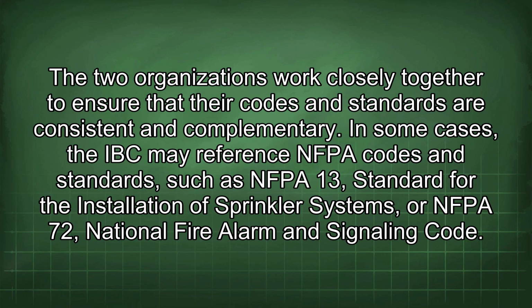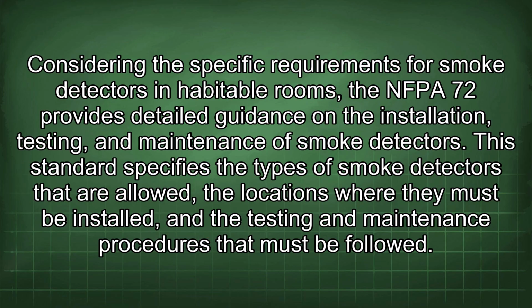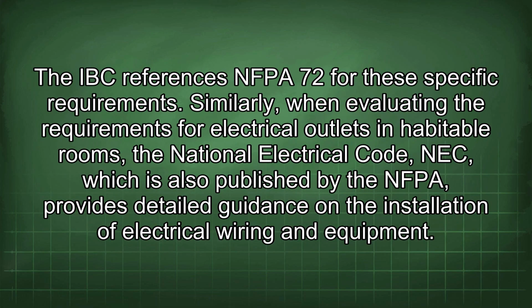In some cases, the IBC may reference NFPA codes and standards, such as NFPA 13, Standard for the Installation of Sprinkler Systems, or NFPA 72, National Fire Alarm and Signaling Code. Considering the specific requirements for smoke detectors in habitable rooms, the NFPA 72 provides detailed guidance on the installation, testing, and maintenance of smoke detectors. This standard specifies the types of smoke detectors that are allowed, the locations where they must be installed, and the testing and maintenance procedures that must be followed. The IBC references NFPA 72 for these specific requirements.